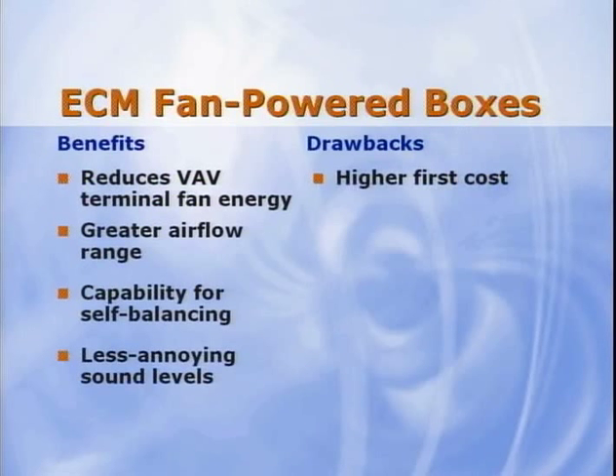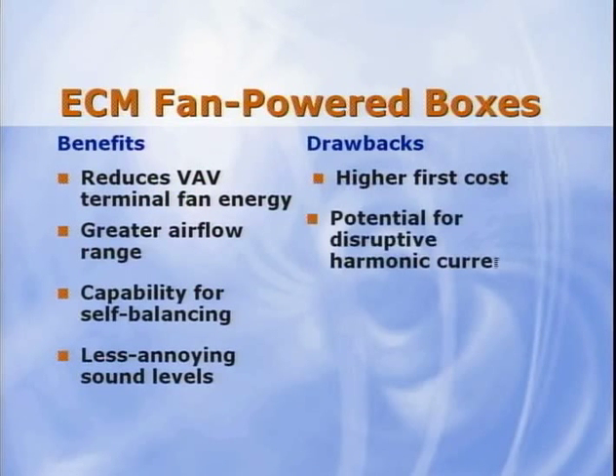Finally, the soft start nature of the ECM allows the fan to ramp up slowly when activated. This minimizes the distraction of the fan cycling on and off in a parallel fan-powered box. But you want to consider the potential for disruptive harmonic currents. Determining whether harmonic currents will cause a problem in a particular building requires review of the electrical system before it's installed so that appropriate steps can be taken then.